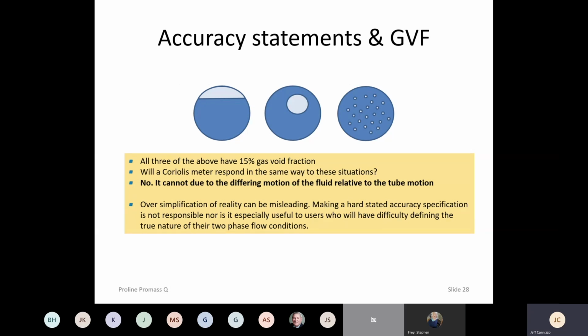The third thing I want to talk about with the Q meter is entrained air. There's all types of entrained air. You see in the picture here, that's 15% gas void fraction. So that's 15% entrained air. And it occurs in all different shapes and forms. Some nicely mixed, some in slugs, others forming at the top of a pipe. So the meter is not going to handle these types of situations the same. It's all going to be different.